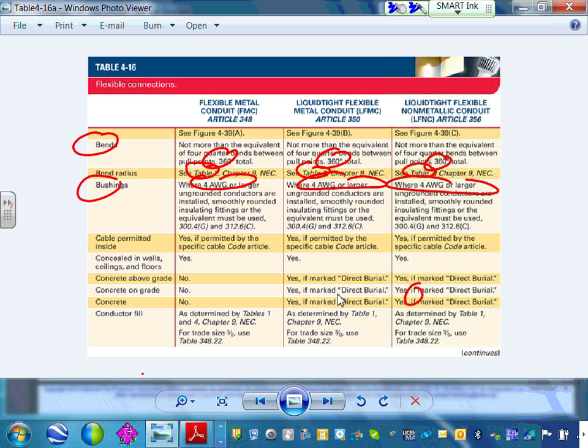For all conduits, do you need them? The only time you need them for smaller than number 4 - can anybody guess? If you have a threaded conduit, with a threaded conduit and not a threaded connector, the threaded conduit sticks inside the box with a little connector here and a little connector inside, so the thread itself is completely exposed in the box. They do this sometimes when they wire. That's the only time you need a bushing for every size wire.